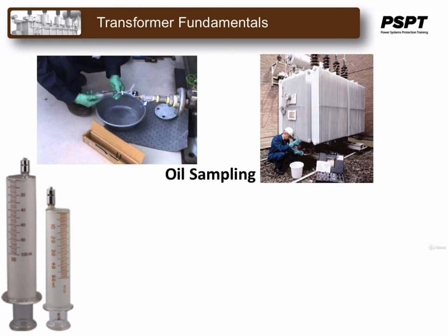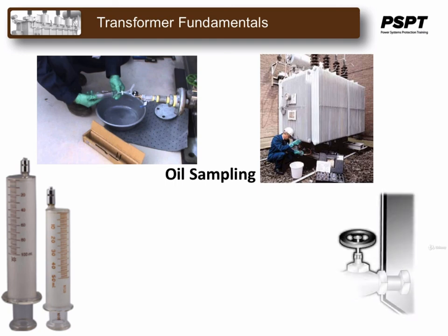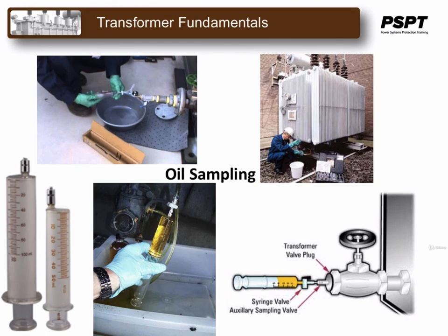If sampling the oil is unavoidable when the outside temperatures are at or below 32 degrees Fahrenheit or 0 degrees Celsius, it should not be tested for water content or any properties that are affected by water, such as dielectric breakdown voltage. For dissolved gas analysis, an elaborate procedure must be followed, including the use of glass syringes, with strict adherence to sampling protocol to ensure that the concentration of dissolved gases is not influenced in any way by the sampling procedure.